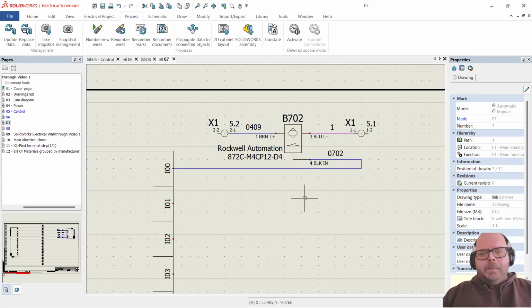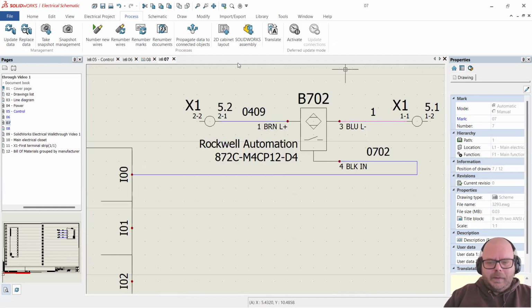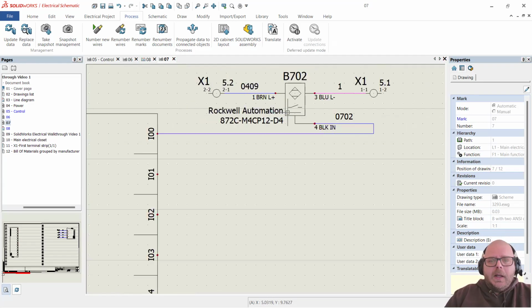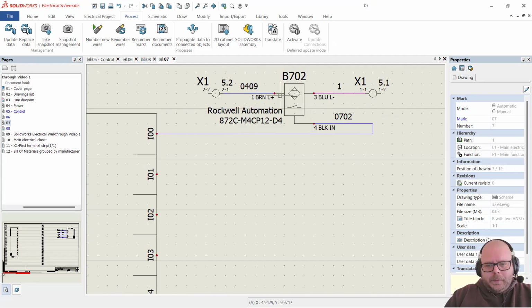That's cool. But again, notice, this is kind of crowded with text. That shouldn't matter. Crowded with text means we have a ton of description on here. It actually, believe it or not, as crowded as it looks, makes it clearer. As long as, like I said, certain text we want to shrink, like I could probably make this part number and stuff smaller. I could do even better with this symbol, with this layout, because it was originally IEC and meant to be horizontal. I could move these connection points so that it makes more sense. Probably shrink the whole symbol down so that it makes more sense.